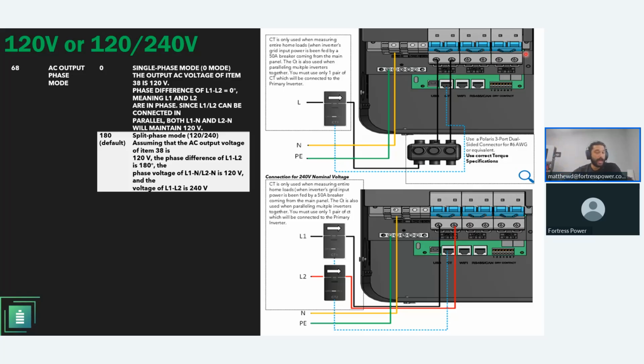Now, if you were going with that option, using a 120 feed and a 120 volt output, then you would have to go into the LCD under parameter 68 and set that to 0, right? 0 for single phase mode. And then alternatively, for the 120/240 split phase, you would use CT1 and CT2, right? And then just feed directly into the inverter without any Polaris plugs or anything like that. And again, reminder, you only need to use the CTs when you have essential loads. In a whole home backup scenario, you don't need the CTs.